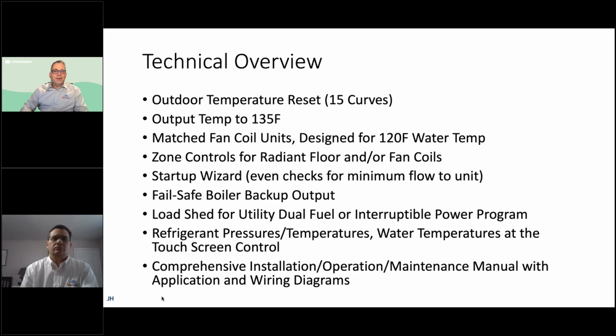We found out on some of the early installations, it even checks to make sure your piping is not sized to too small diameter. So if it doesn't have the flow rate needed, it will tell you during that startup, sorry, I can't get the flow rate that the unit needs. And in some cases, that might mean upsizing the piping. Hopefully we've looked ahead and everybody's attended the training videos, so we know up front what size piping we need, but it does check for that.